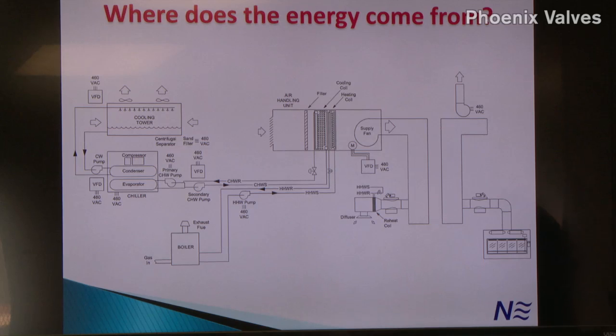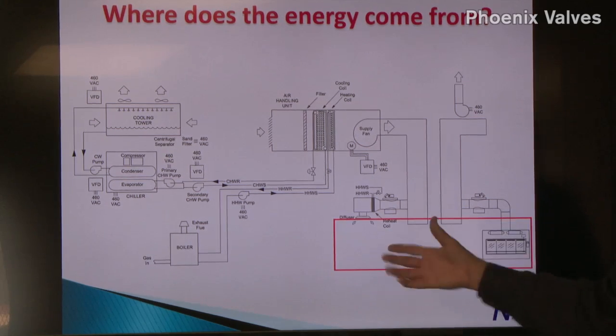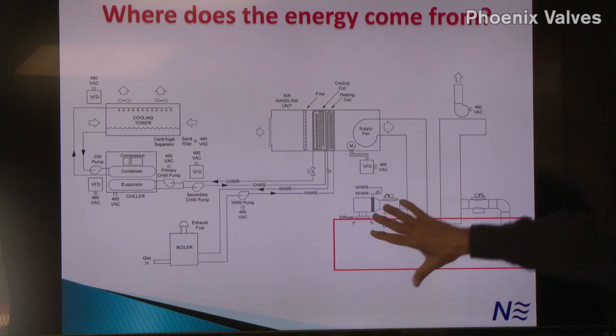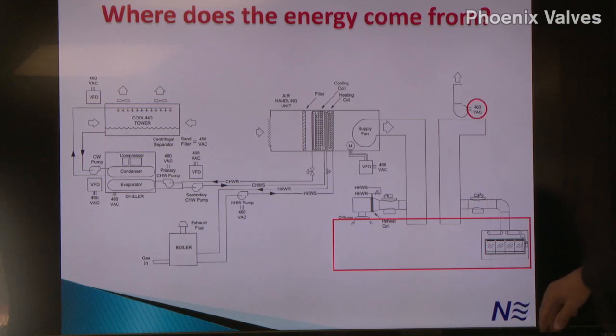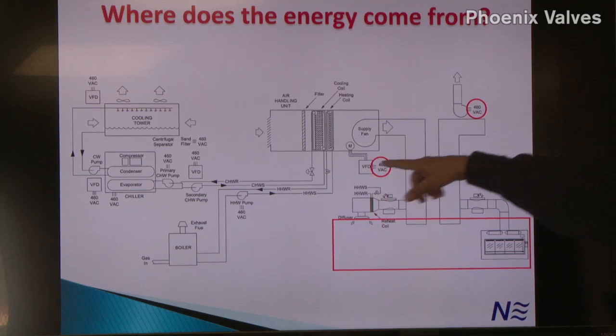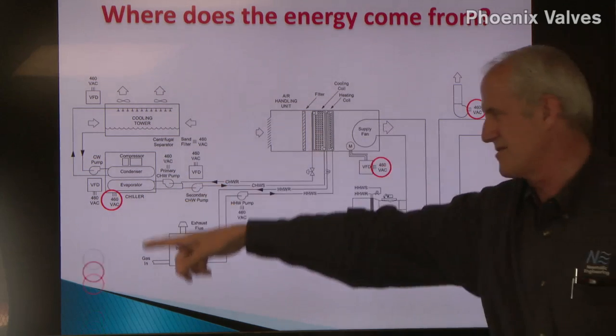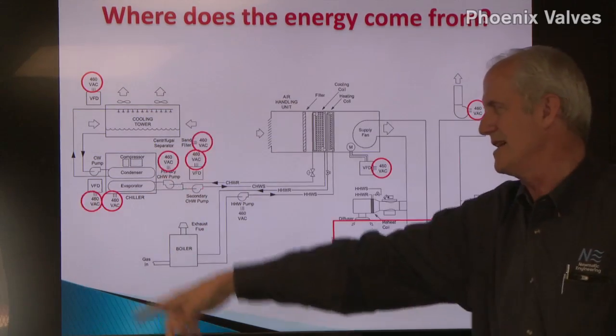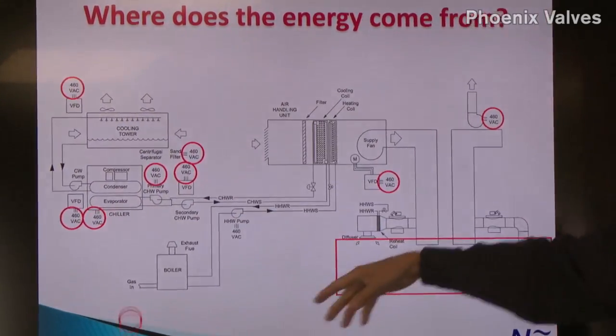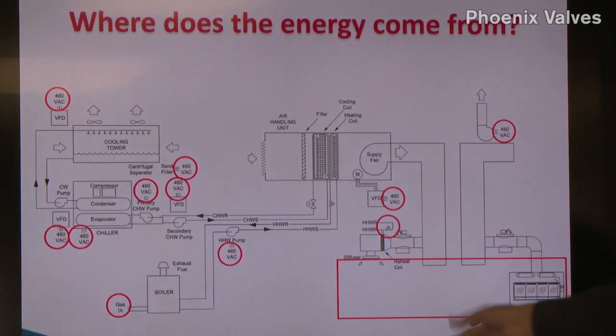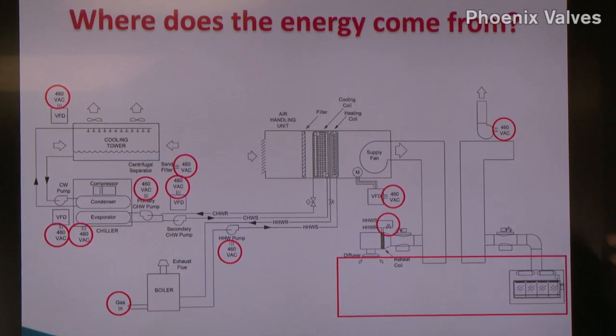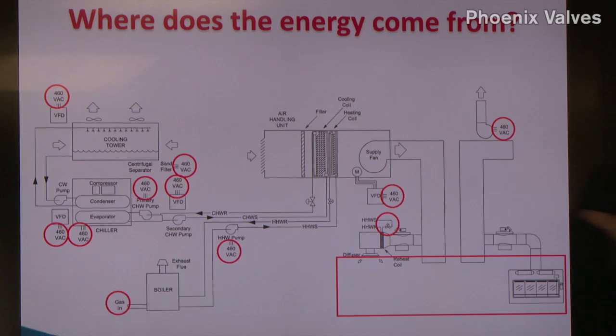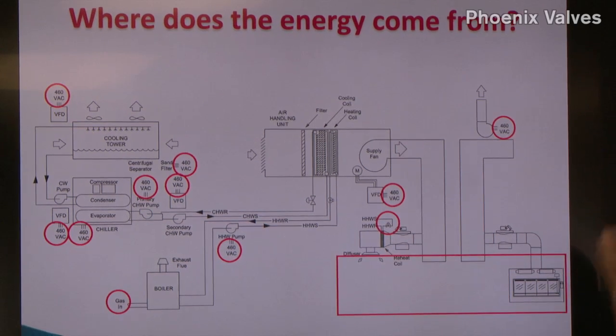Another point, when they say how much energy does the Phoenix valve use, you can't just measure here and say it's using more energy, because when you turn down a little bit of airflow in here, your exhaust fan will slow down, your supply fan will slow down, your chiller will slow down, your cooling tower will slow down, your condenser water pumps and chilled water pumps will slow down, your boiler and heating hot water pump will slow down and use less reheat. So it's hard to say where the energy comes from, but suffice to say there's a whole lot of energy involved with every drop of air you put in the building. So every bit we can save has a big consequence.